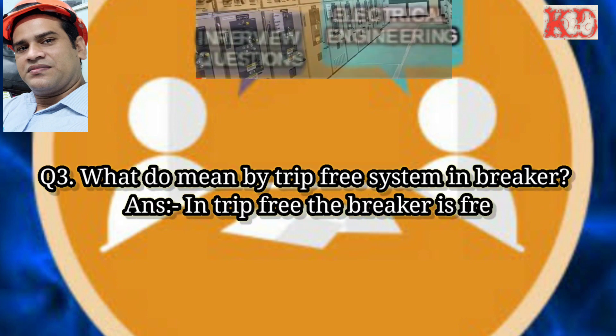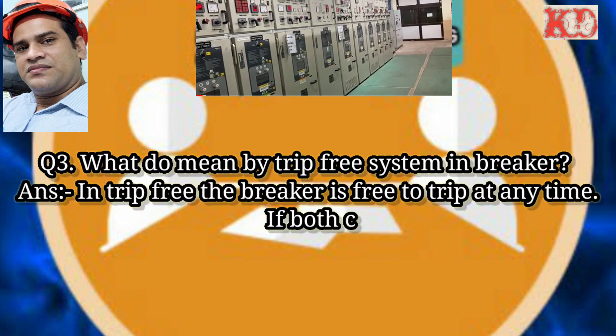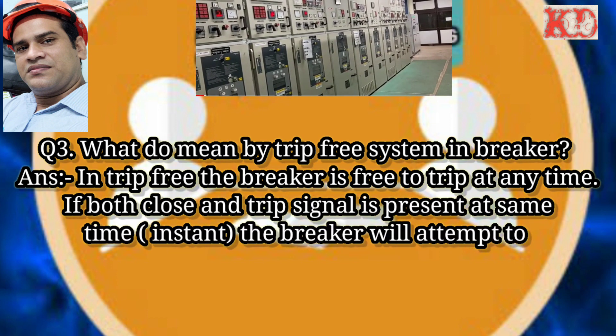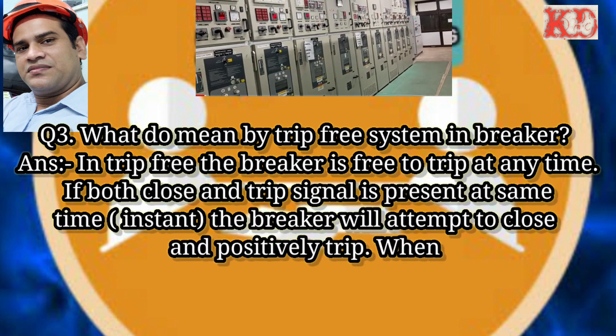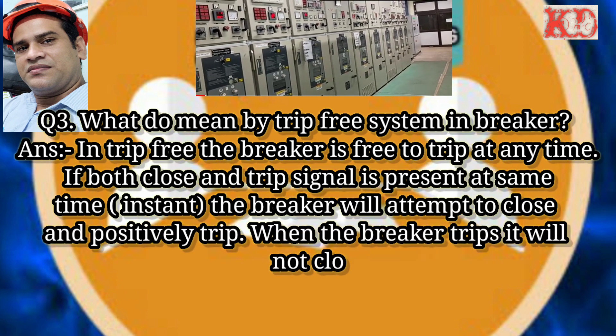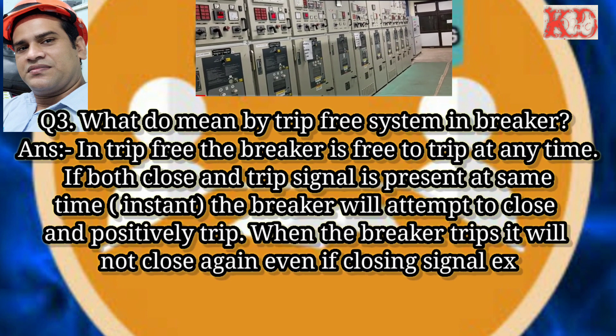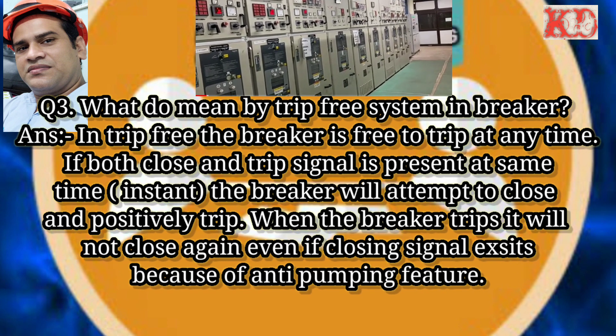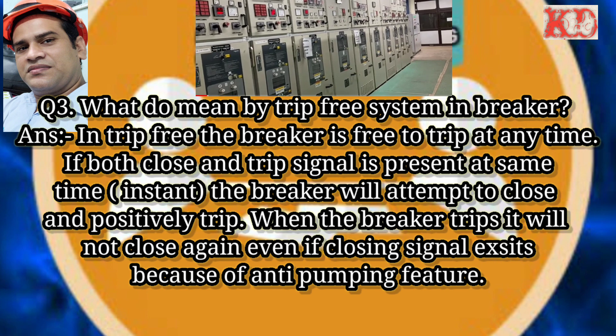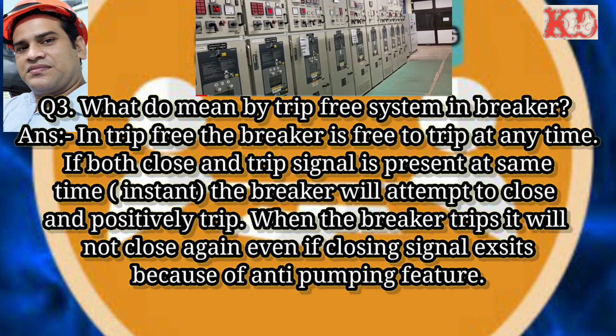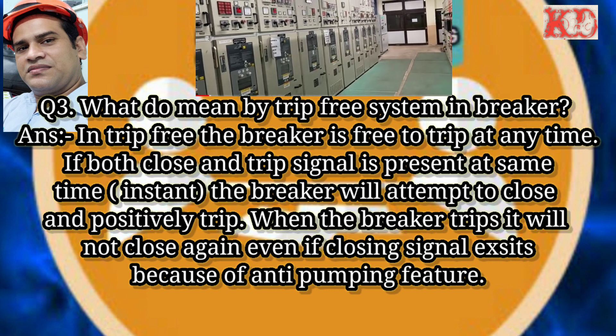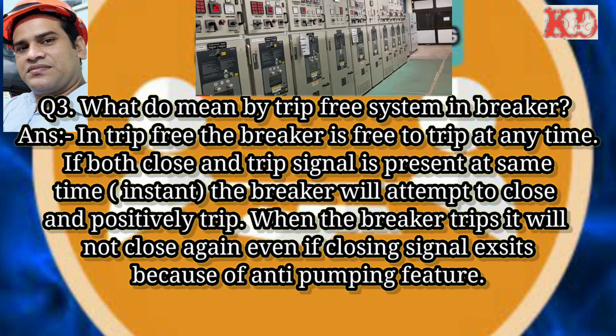Question number three: what do you mean by trip free system in a breaker? Answer — in trip free, the breaker is free to trip at any time. If both close and trip signals are present at the same time, the breaker will attempt to close and positively trip. When the breaker trips, it will not close again even if the closing signal exists, because of the anti-pumping feature.